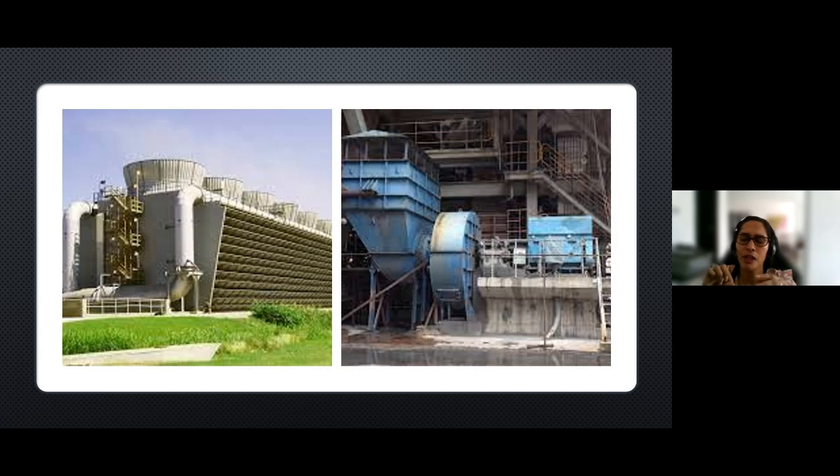Going back to my experience as well. So I remember when I was in a power station, one of our relevant points to try to consider improving boiler efficiency was the relevance of an optimized air-fuel relationship or ratio to improve boiler combustion and reduce oxygen excess. This condition makes us focus on different conditions like power consumption of the fans, performance of the fans, and also performance of the boiler. We have to integrate different processes in order to realize that we need to emphasize reducing the power consumption of the primary and secondary fans to reduce the waste of energy or waste of power in that particular equipment.